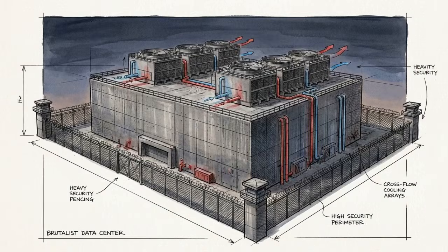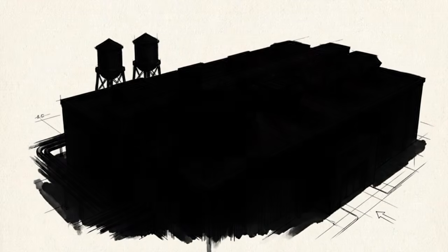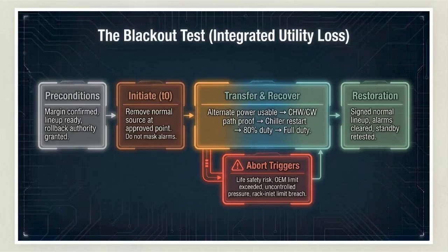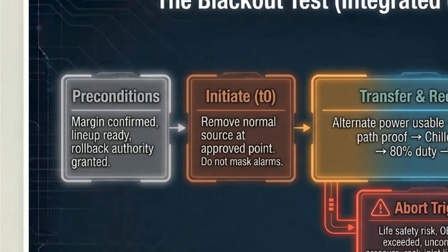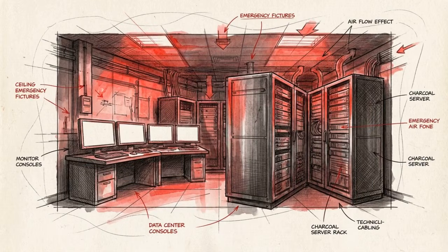The ultimate proof of a cooling system's resilience is the integrated utility loss test. This live simulation measures whether the entire plant can survive a total blackout and restore flow without breaching the IT thermal envelope. This flowchart maps the blackout test sequence. Before pulling the plug, the team must confirm strict Level 1 preconditions: a verified thermal margin, a normal operating lineup, and a synchronized time zero timestamp established across every data log. At time zero, normal power is severed.